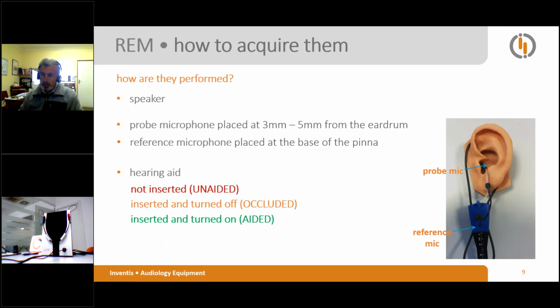So the two probe microphones, one for each ear, allow the hearing care professional to measure the signals arriving at the eardrum of the patient through a silicone tube inserted in the ear canal. The two reference microphones, one for each ear, record the signals arriving at the base of the pinna of the patient under test. And of course, it is very important to have a hearing aid. The signals acquired allow not only to evaluate the performance of the hearing aid directly in the ear canal of the patient, but also to understand how to adjust the gain of the hearing aid to the desired levels, comparing the curve acquired to the target.